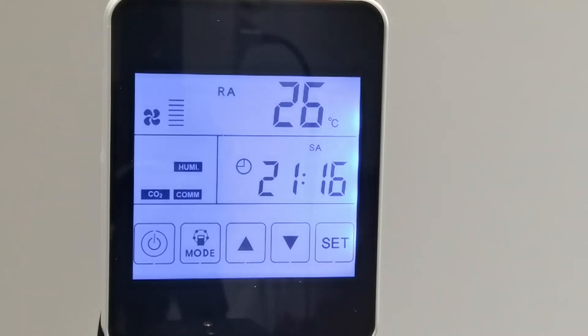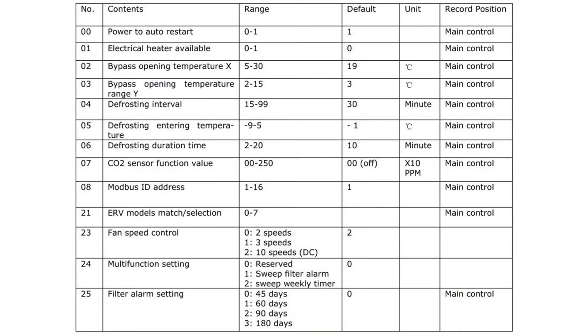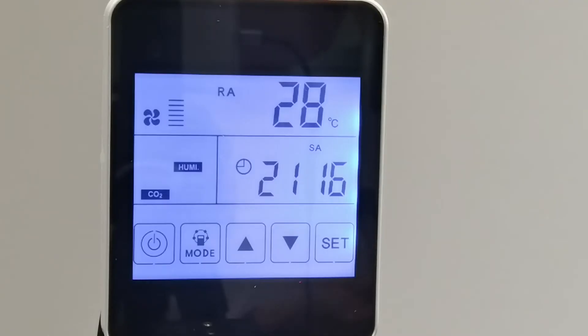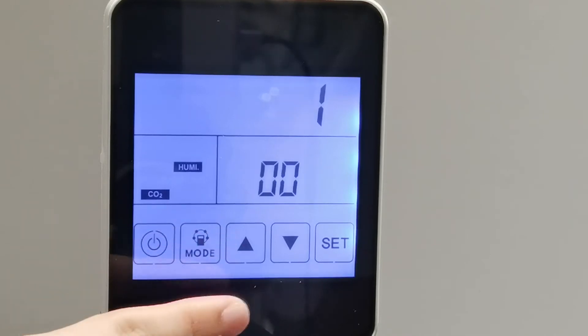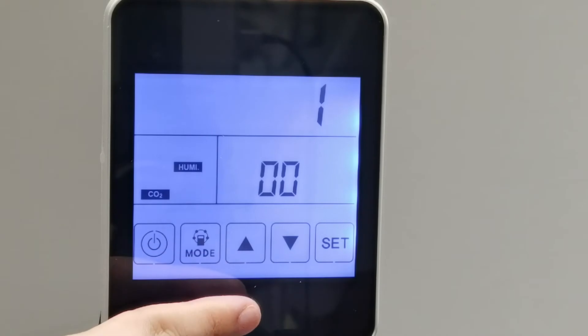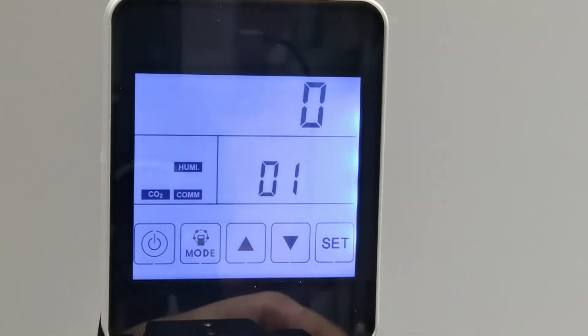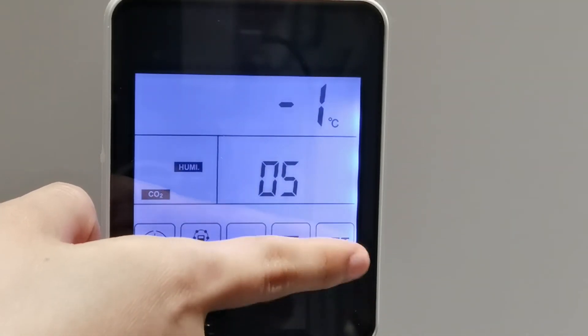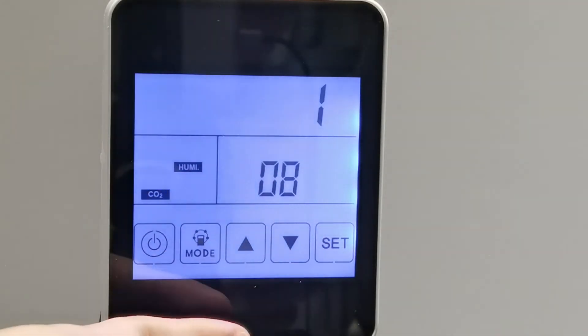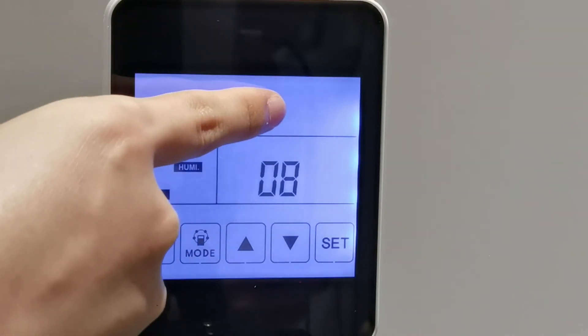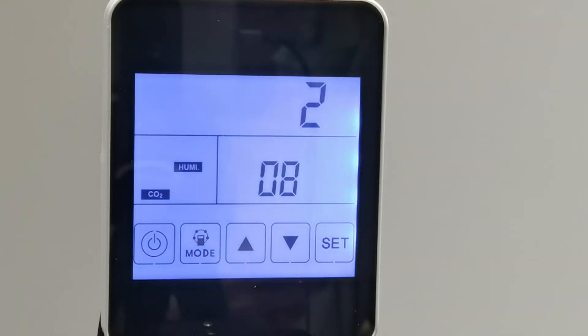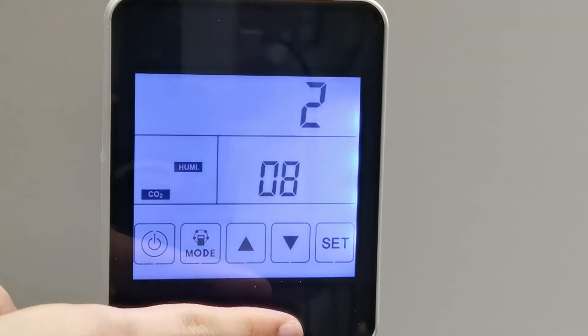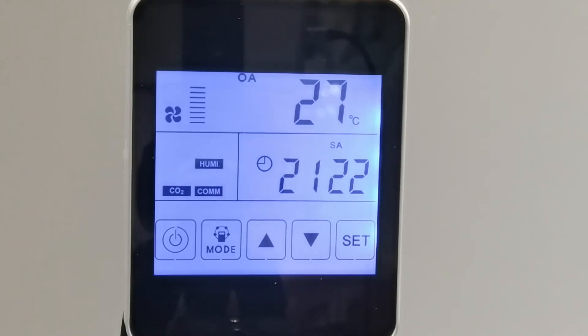Now let's move to the parameter setting. Here is a direction chart. The number on the left indicates which functions are specified. To set the functions, press the mode button for 6 seconds to enter the parameter setting interface. Press the set button to change the parameter — the number ranges from 00 to 25. After choosing the correct parameter number, press the mode button. The parameter value will flash at the right corner. Press the up and down button to change the value, then press the set button to save.